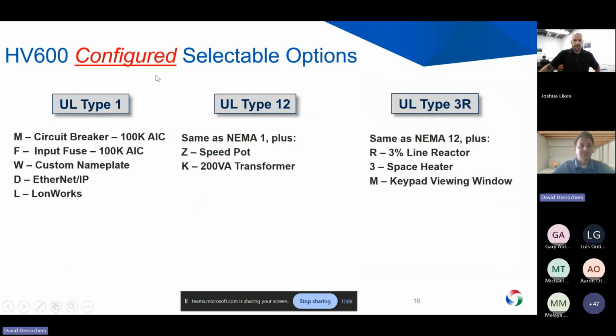On the configured selectable options, you put it in a box and then you can add on different options that you might like with the drive. That'd be circuit breaker. You could add on the 3% line reactor like we discussed if you go all the way to the 3R. Each one builds as a tier. So Type 1, you can get all this. Type 12, you can get all this plus all this. And then 3R, all of this plus these additional ones.